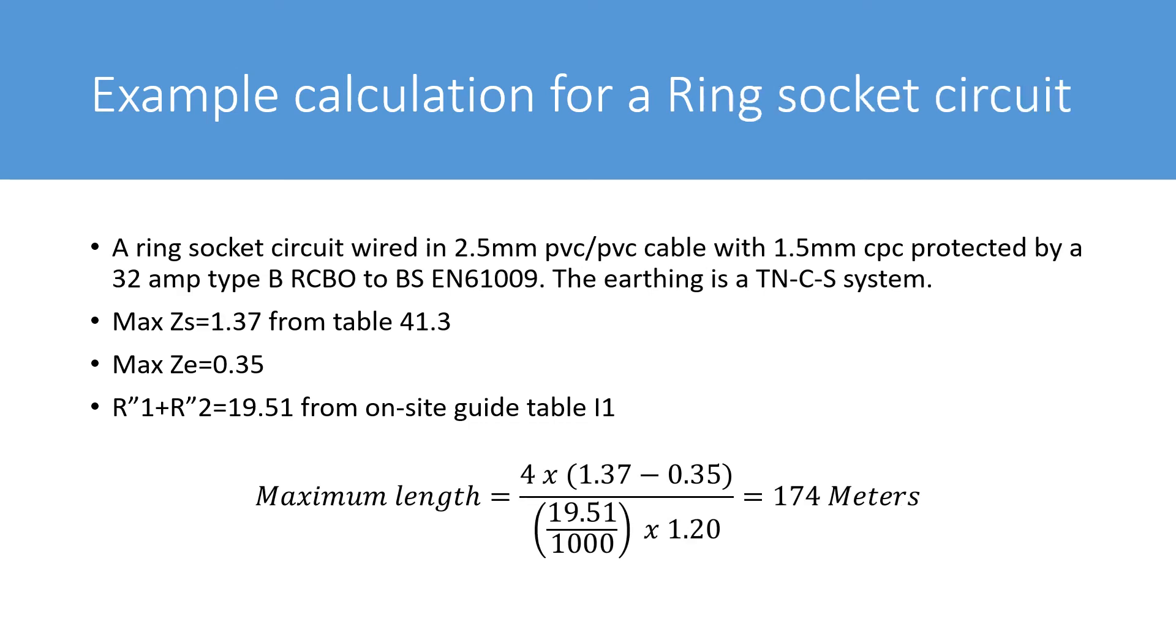So here we have another example calculation, but this time for a ring socket circuit. A ring socket circuit wired in 2.5 mm PVC-PVC cable with a 1.5 mm CPC protected by a 32 amp type B RCBO to BSEN61009. The earthing is a TNCS system.